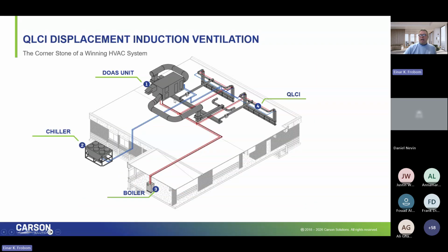Here's a more elaborate schematic of that system coming together, where we have the DOAS unit that happens to be outside rooftop mounted, doesn't have to be. But in this example, rooftop mounted, outside air is coming down this central corridor. And then we have the branch takeoffs that are feeding the terminal units in the classroom, typically along the exterior wall. And then you can see these bullhorn connections. Those represent the exhaust air connection for each room that is pulling that exhaust air back to an energy recovery based DOAS unit.